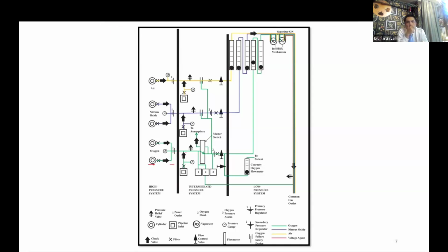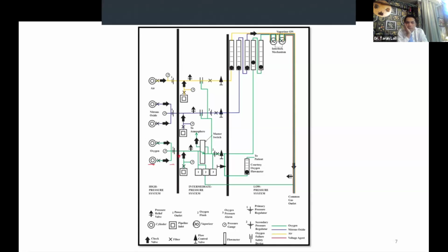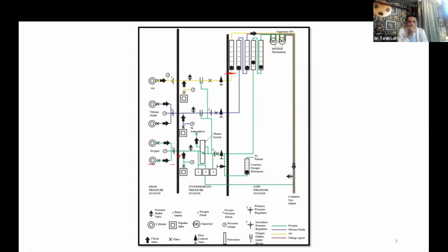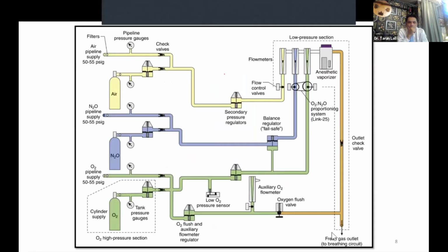So from the output of the regulator till just before the flow valve is your intermediate pressure system. And beyond the flow control knob, it is all low pressure system. This particular picture that you see is from Dorsch, and we also have the same thing in Miller's, slightly more colorful, but essentially it says the same things. The cylinder is your high pressure system. Beyond that, till your flow control knobs is the intermediate, and beyond the flow control knobs is your low pressure system. Because this will be asked in exam, you should be able to show this on the machine.